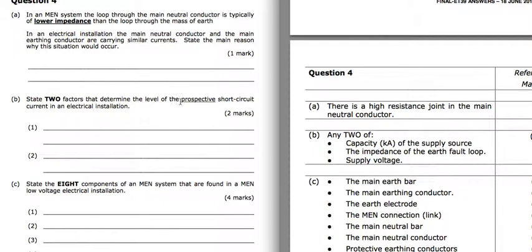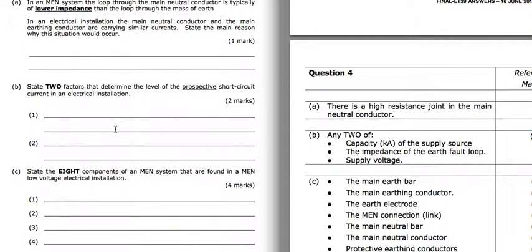Two factors that determine the level of prospective short circuit current in the installation. Again, we've seen this question before. It's all about the capacity of the supply, how many kiloamps the supply can give out, the impedance of the earth fault loop, and the supply voltage.